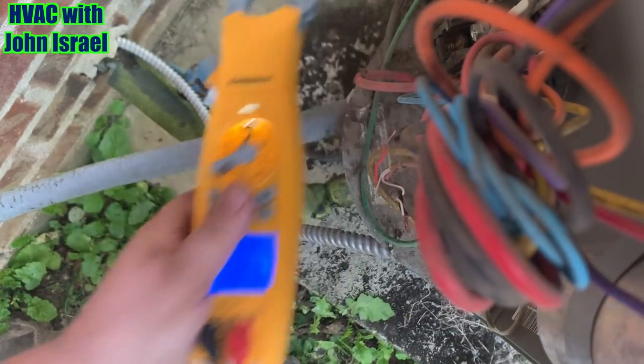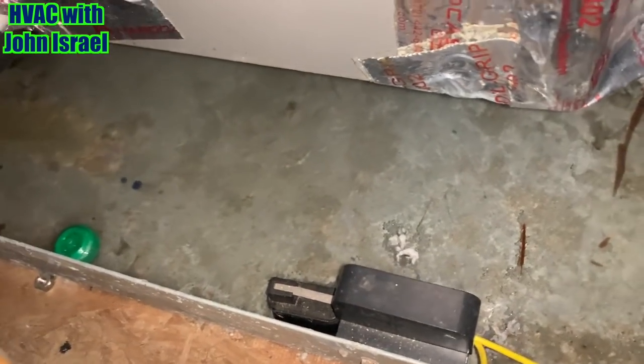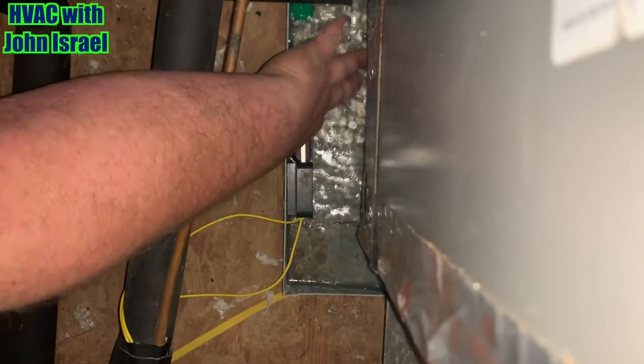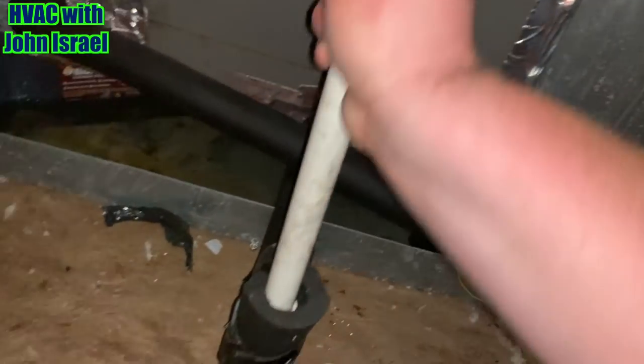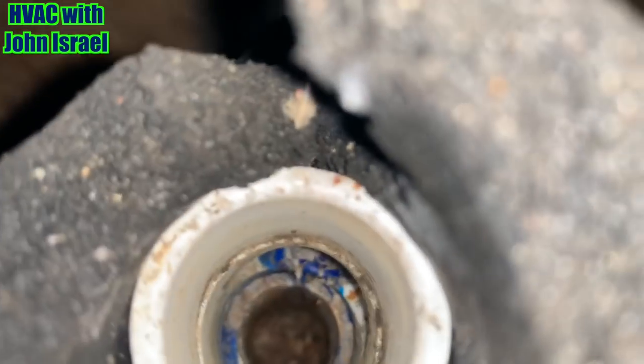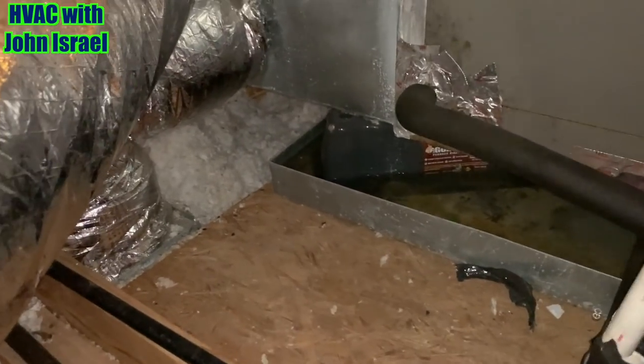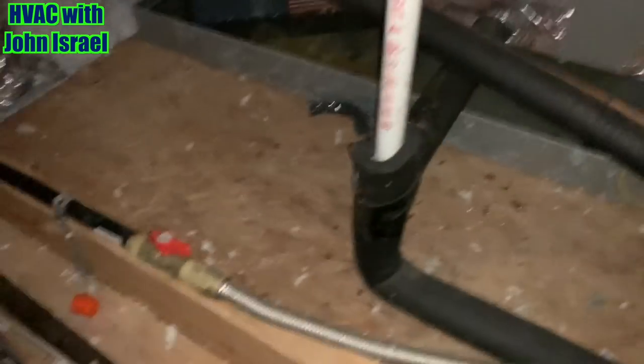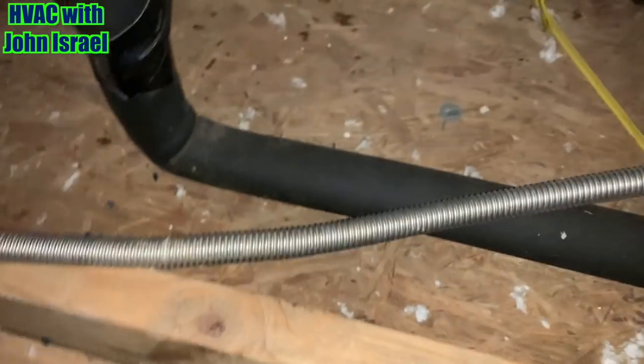Only 3 volts — so no 24 volts. Okay, we'll have to go in the attic. We got a pan full of water. He must not have seen that last night. The float switch is definitely lifted. Looks nasty down in there.